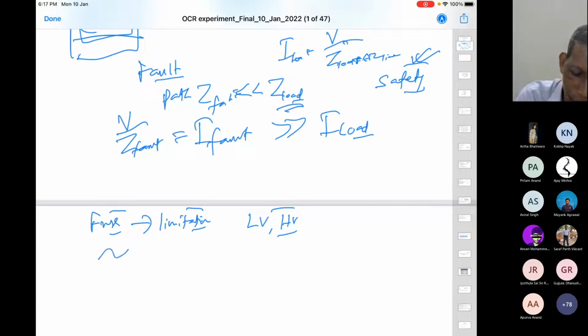So if you think about the fuse here, what happens then, it melts at one point, and finally the melting or breaking can be more and more. The separation between these two ends will be more and more. The arcing persists, and the evaporation of that fuse element becomes more and more till we get restriking voltage against the system voltage, 400 volt, 400 kV or whatever, by √3, the phase to neutral voltage. Therefore, depending upon the voltage, we require this, because this side is, let us say, the fault, meaning grounded, and this side is your system, the substation side. So this is 400 by √3, let us say.